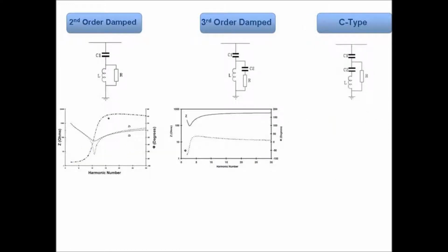And then damped passive filters. Basically these are similar to the previous lot, except there's a resistance brought into it, and the resistance tends to spread out the effect of the filter. So you won't get the same peak, like you won't be able to take out an individual harmonic in the same manner. It won't remove the fifth on its own just as well, but it will take the fourth and the sixth beside it a little bit as well. So it can be useful if you've got 3 or 4 harmonics all together. You can reduce them all a little bit, but you won't ever probably eradicate them completely. And again, these have got various types. There's second order, third order, and C type. And a lot of them that tend to be designed today tend to be C type filters.